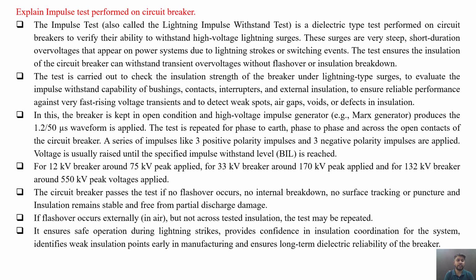Voltage is usually raised until the specified insulation withstand level, that is the basic insulation level (BIL), is reached. For a 12 kV breaker, around 75 kV peak is applied.